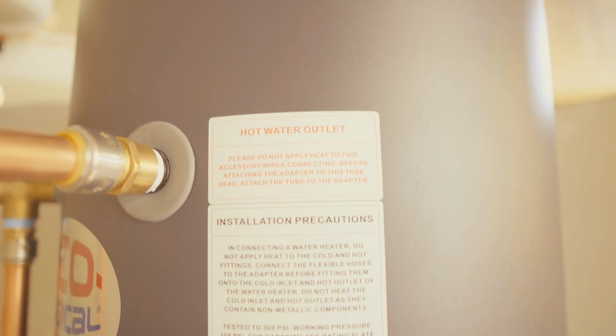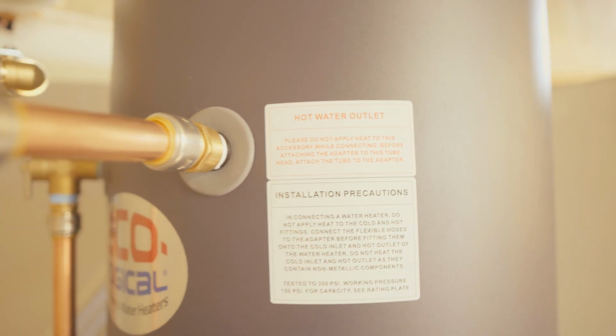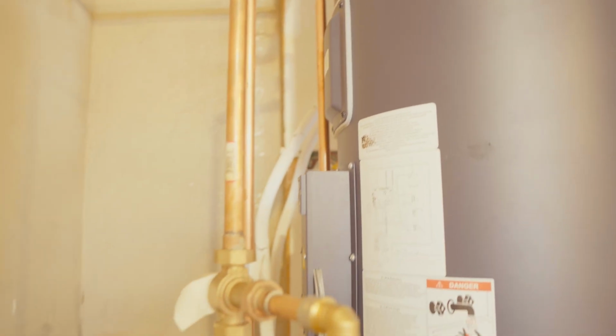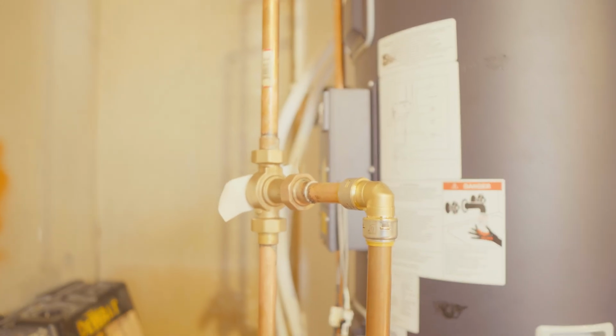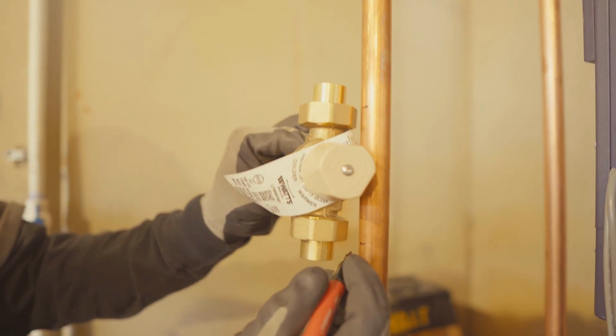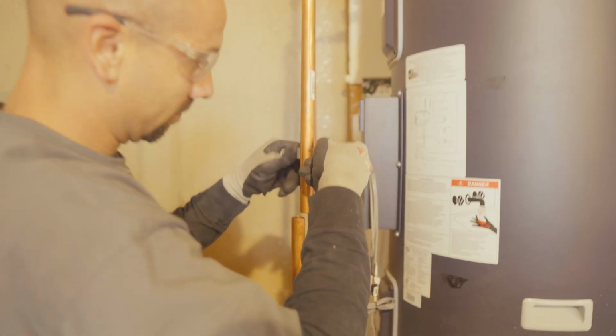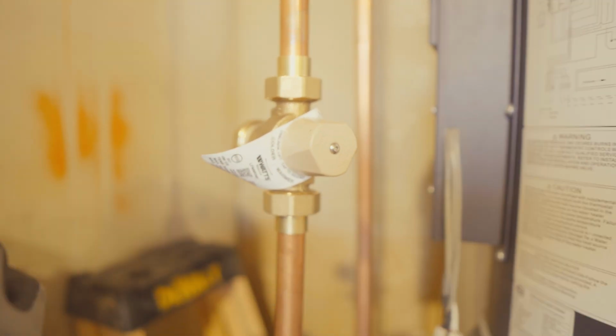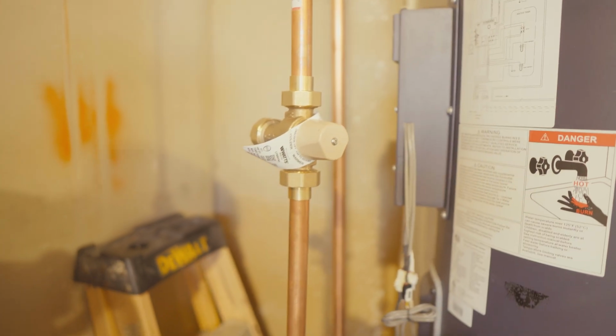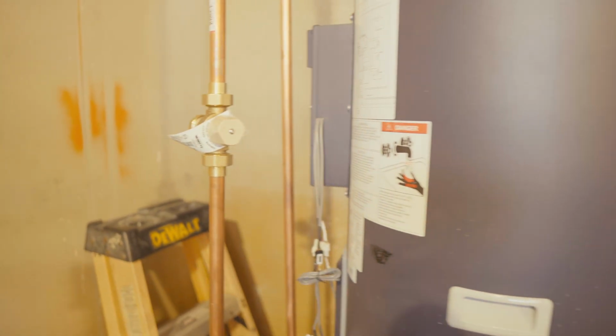For the hot water outlet, we attach a female fitting to the tank's hot water port, then use an elbow to route the line downward to the other side of the thermostatic mixing valve. At this point, the hot and cold water piping join together at the valve. We solder and sweat the copper piping to create a secure, leak-free connection.